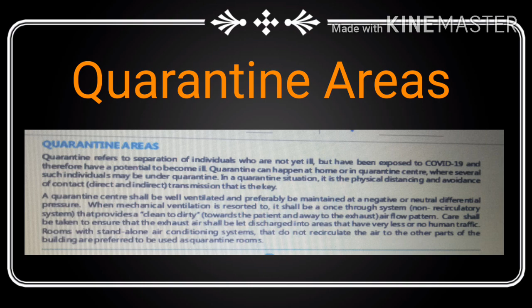A quarantine center shall be well ventilated and preferably be maintained at a negative or neutral differential pressure. When mechanical ventilation is resorted to, it shall be a once-through, non-recirculating system that provides a clean to dirty airflow pattern, from the patients towards the exhaust. Care shall be taken to ensure that exhaust air is discharged into areas that have very little or no human traffic. Rooms with stand-alone air conditioning systems that do not recirculate the air to other parts of the building are preferred to be used as quarantine rooms.